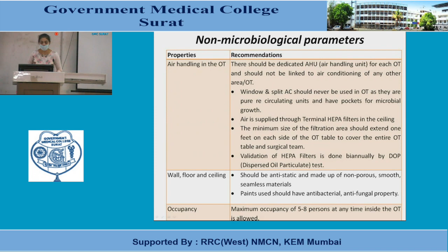The minimum size of the filtration area should extend 1 foot on each side of the OT table to cover the entire OT table and the surgical team. Validation of the HEPA filter is done biannually by the DOP, dispersed oil particulate, test. Wall, floor and ceiling should be antiseptic or antistatic and made up of non-porous, smooth, seamless materials. Paint used should have antibacterial, antifungal properties. Occupancy: a maximum of 5 to 8 persons at any time inside the OT is allowed.